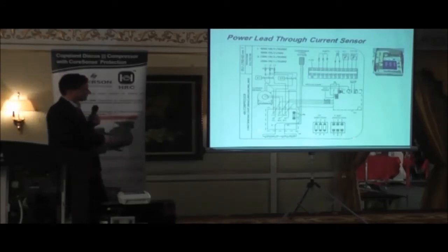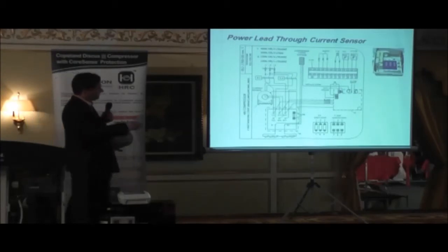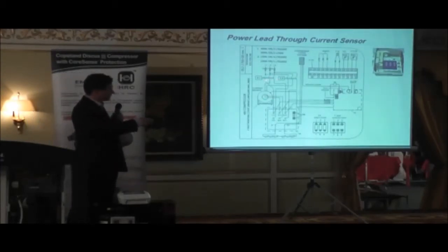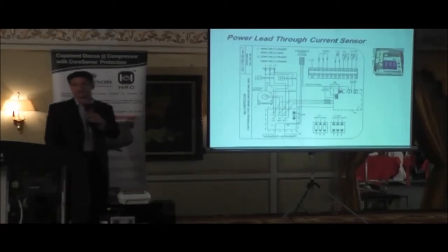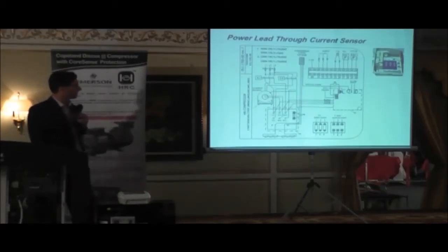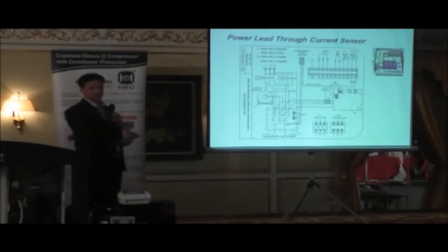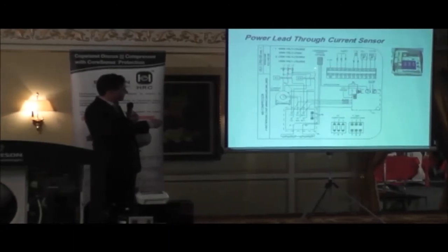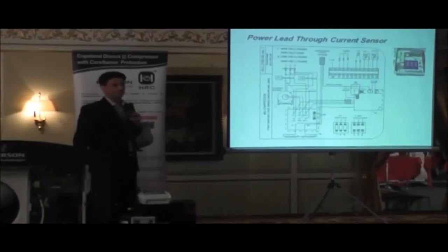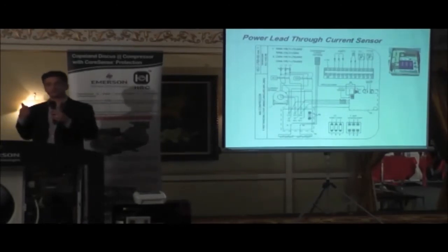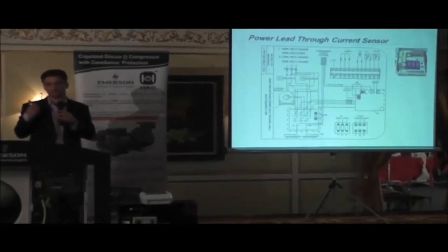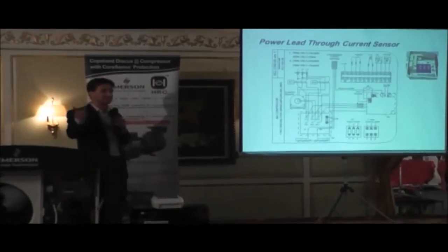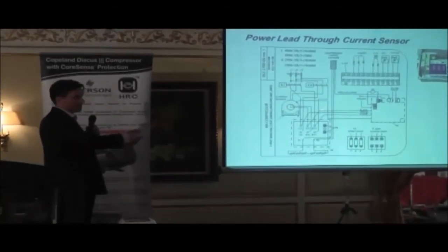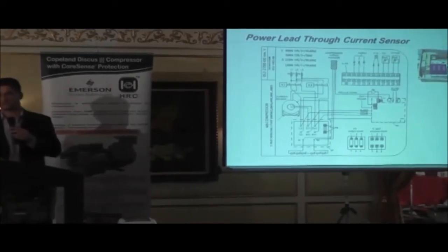This is the wiring diagram label in the T-box, when you open the T-box. And it clearly illustrates here for the current sensor that you have to wire one of the phases through the current sensor. Okay? In this example here, this is a part-wound motor. So you would need to take the second line on your primary and the second line of your secondary through the current transformer so that it will read the correct amperage. If you've got a star or a delta connection, you obviously would only take one phase through that current transducer.